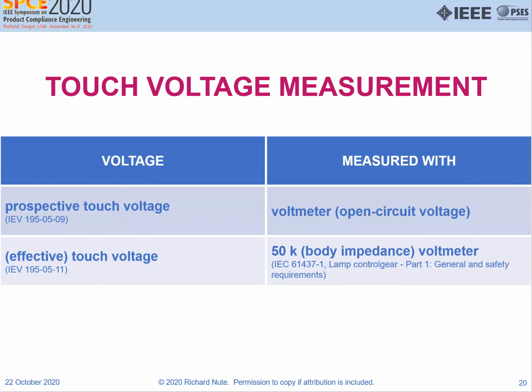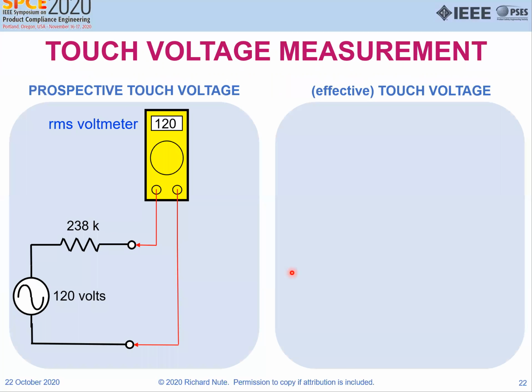We can measure touch voltage. And we have prospective touch voltage. In one case, we measure with a voltmeter, it's open circuit voltage. Effective touch voltage, which is from 61,437, which is the other standard, is usually measured with a 50,000 ohm voltmeter. Well, we're going to look at that for just a moment, see what the benefit of that is. First of all, if you're measuring prospective touch voltage, you have 120 volts and a 238K resistor. But remember, a voltmeter is infinite impedance, or close to it, 10 megohms or more. And that's quite a bit more than 238K. So you measure 120 volts, there's no current flowing through this resistor. There's no voltage drop, so you measure the voltage across this.